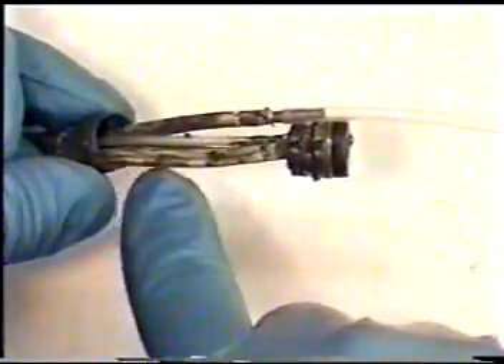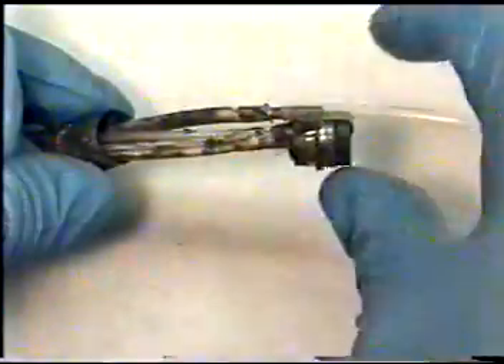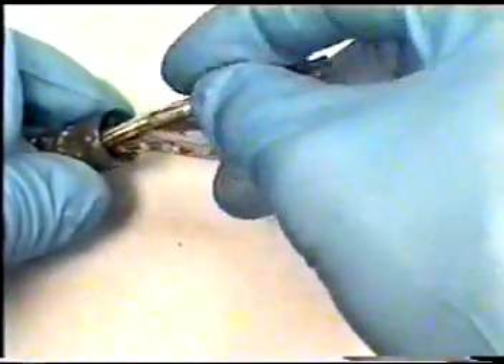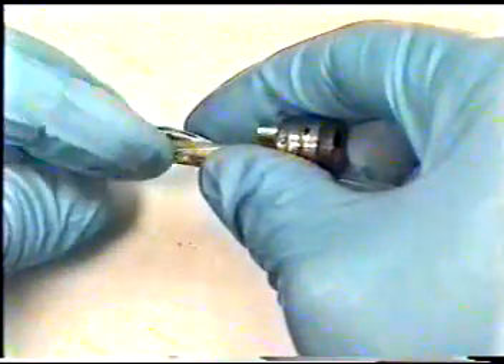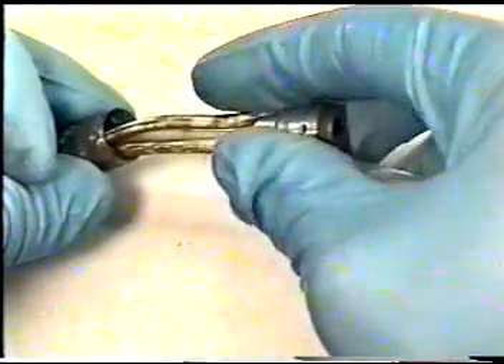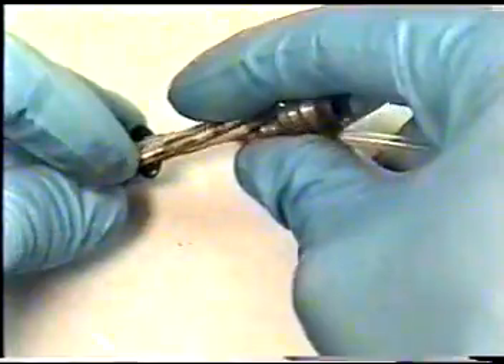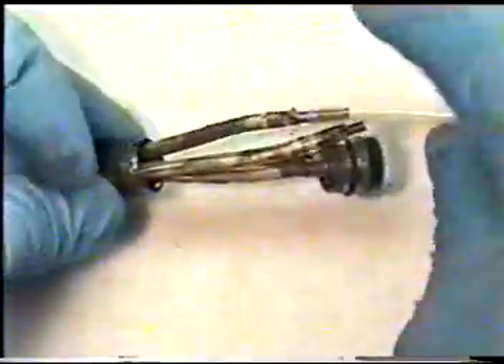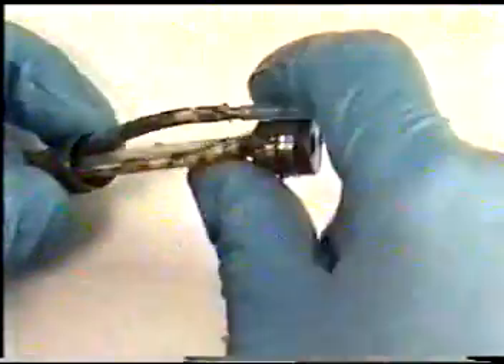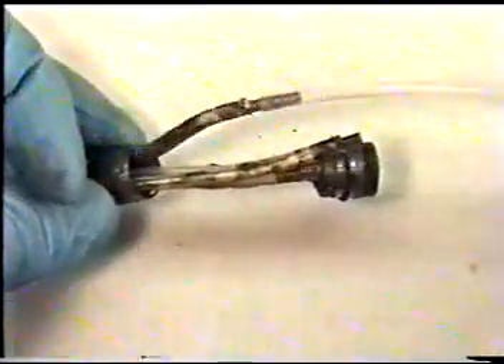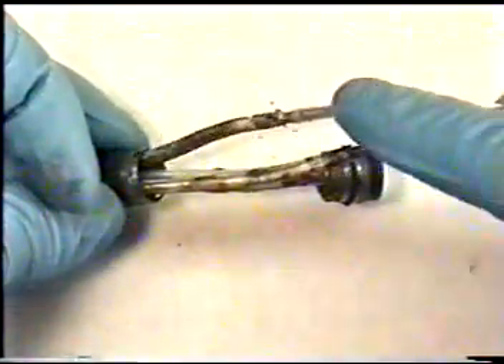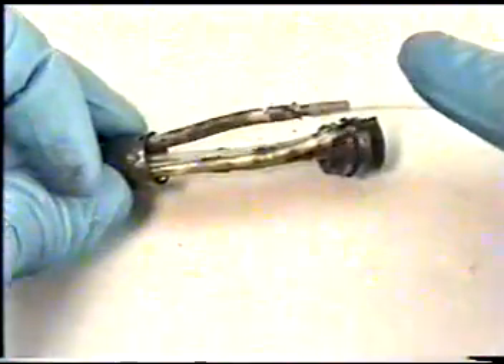If the light guides are pulled through in the wrong orientation to your distal end, it will cause the channels and light guide tubes internally inside the bending section to twist and bundle around, and this will cause serious damage to the channels and light guide bundles and image bundle if it is not placed in the correct position internally inside the bending section and the insertion tube. So we will need to pull through our plastic tubing when we pull through the old light guide bundles.